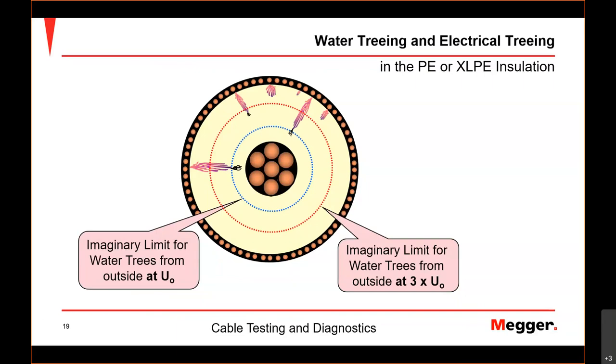Tan delta, what's the length limit with tan delta? Well, that is limited again with the cable capacitance. Tan delta is based on VLF sine wave. Sine wave has 2.5 seconds to charge your cable and 2.5 seconds to discharge again. So whatever this instrument can charge in 2.5 seconds, that's your cable length. And that would be also somewhere within the range of maybe 5, maybe 10 kilometers, very roughly.